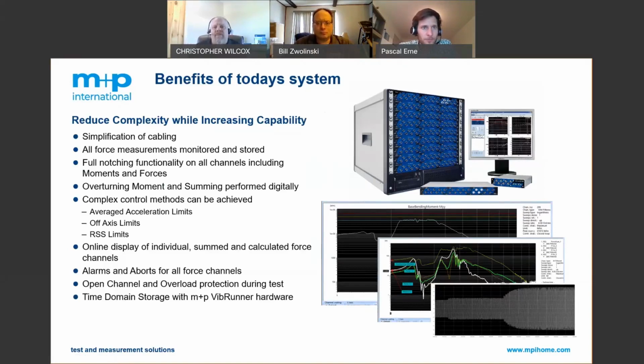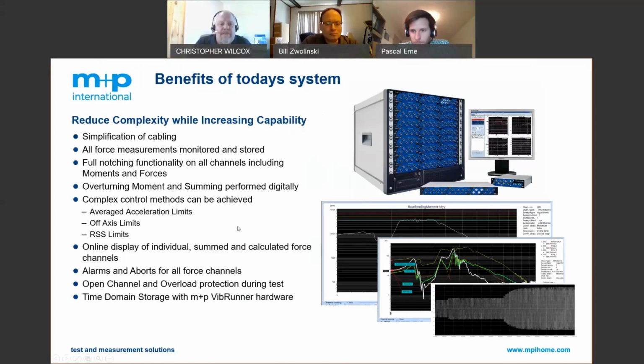Overturning moment and summing are performed within the software, so you can change axis just through the user interface. All the complex control methods are still there: average acceleration, off-axis limits, and root sum squared limits. Everything we do is available online, which I'll show shortly, along with calculated force channels, all while doing time domain storage of every channel including force. This can be very handy for performing a CG or dynamic CG test or verification after a test.